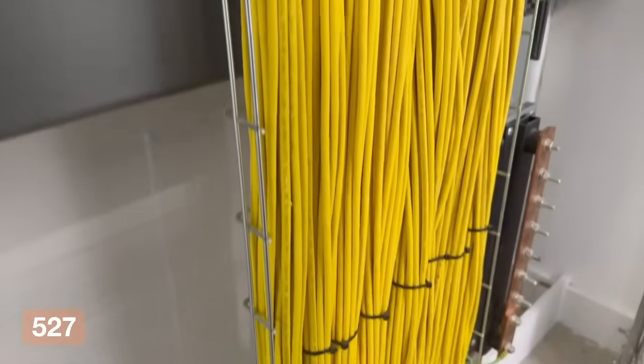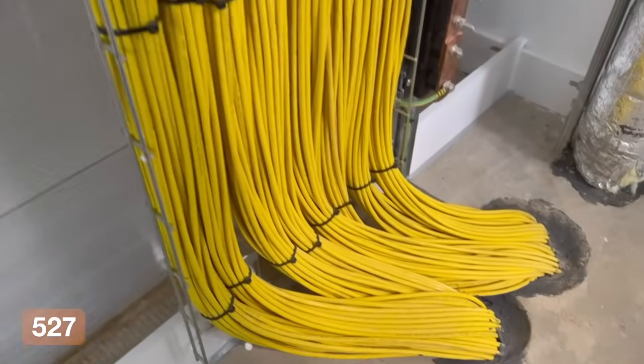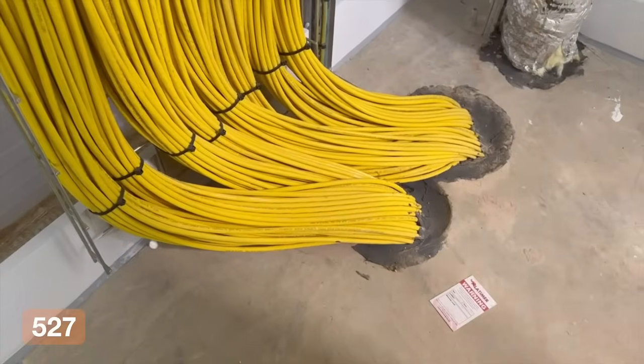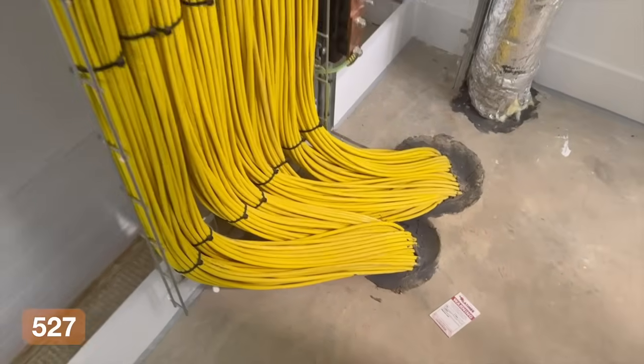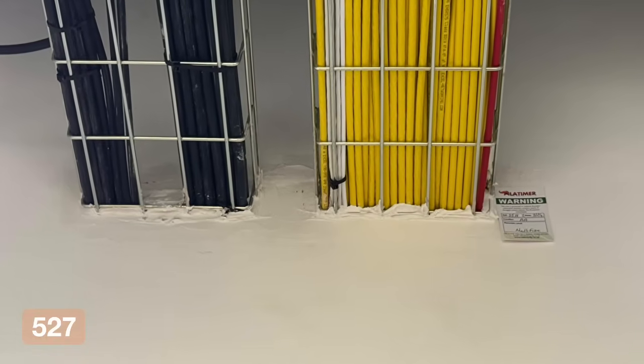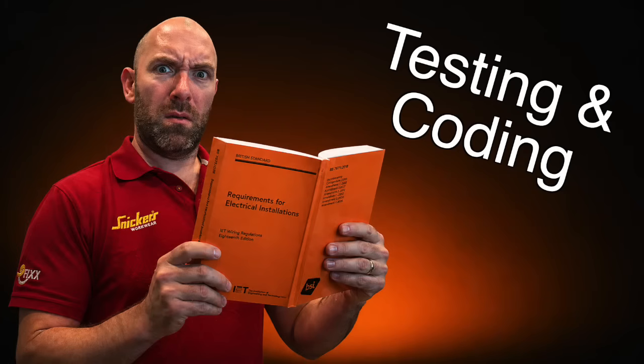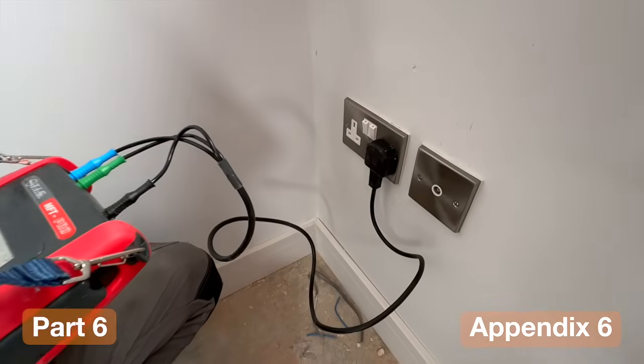There is also a link to Regulation 527, where a wiring system passes through a fire-resisting element. It must be sealed correctly. The opening must maintain the fire resistance of that structure. So this is not just about the cable itself, it is about how the installation behaves within the building during a fire. The way FI codes are used has been adjusted, and this has had a direct impact on how reports are produced on site.